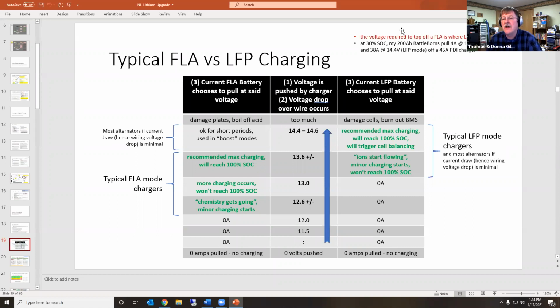As a matter of fact, just last week my Battleborns were sitting at about 30% state of charge, and it's 200 amp hours. When the PDI was running in flooded lead acid mode, outputting 13.6 volts, the charge rate was only 4 amps. I could use the little pendant and hit the boost button, which would cause the voltage to jump up to 14.4. Then suddenly those batteries were pulling 38 amps. So just by having the right mode on the charger, the charge rate was 10x.